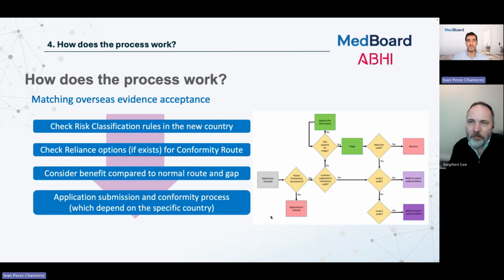One of them that Steve and I used in the work we've done together in the past is Australia. Australia has a very good framework, and you can see by risk class what is accepted. Then you need to consider also the benefit, as you say, Steve, and then you apply the submission and the conformity assessment, which will be very dependent. But one of the two things we want to emphasize is you need to check the risk classification rules in the new country, not where you have the approval already, and then check if there are reliance options, because depending on the classification, the recipient country may accept a 510K or a PMA or nothing. So you have all those options.